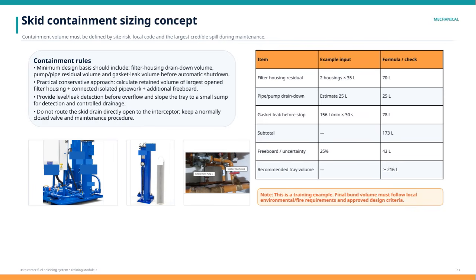It's also important to implement level or leak detection systems before the containment overflows. The tray should be sloped toward a small sump to facilitate detection and controlled drainage. Do not route the skid drain directly to an interceptor without control. Always keep a normally closed valve and a maintenance procedure to manage potential spills safely.